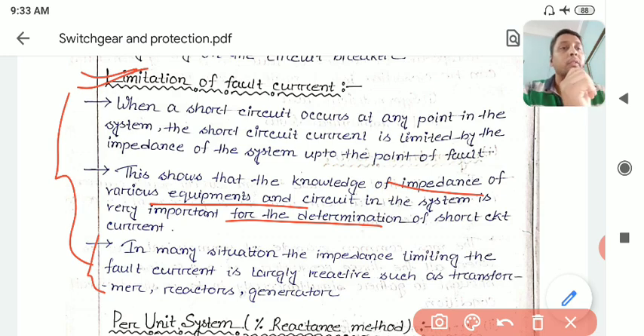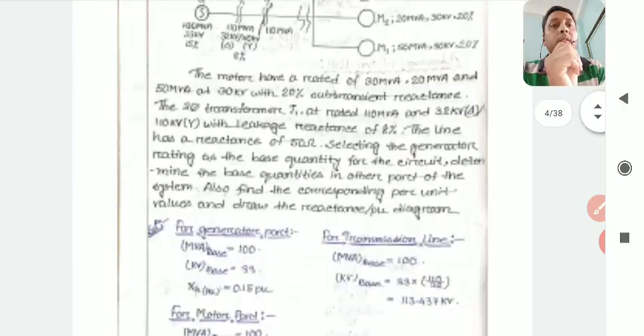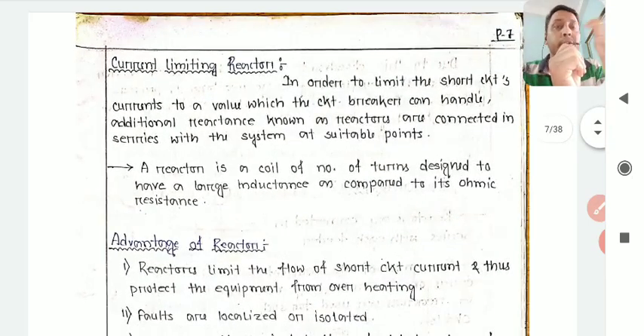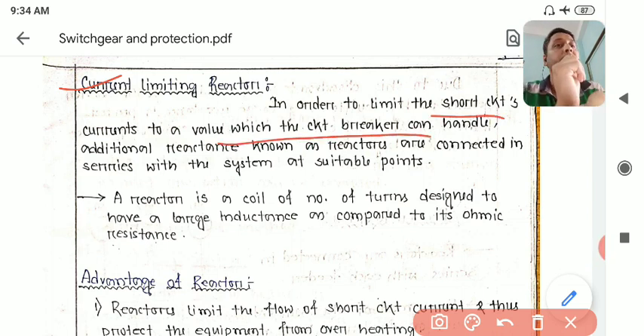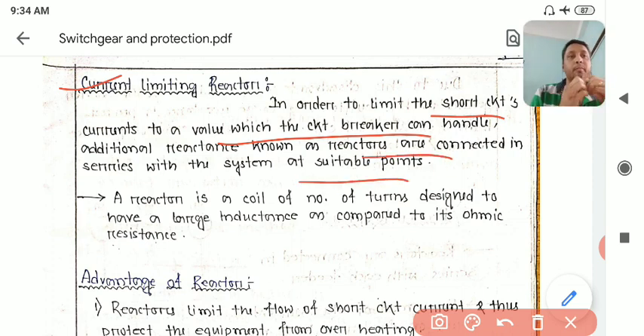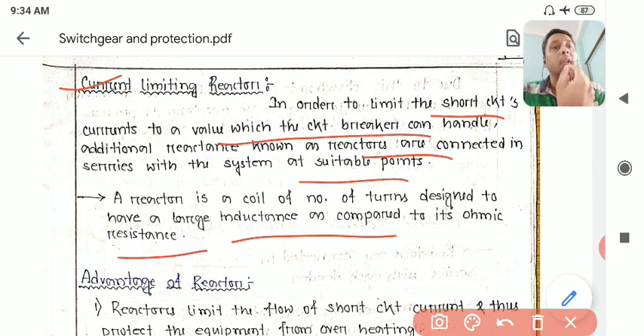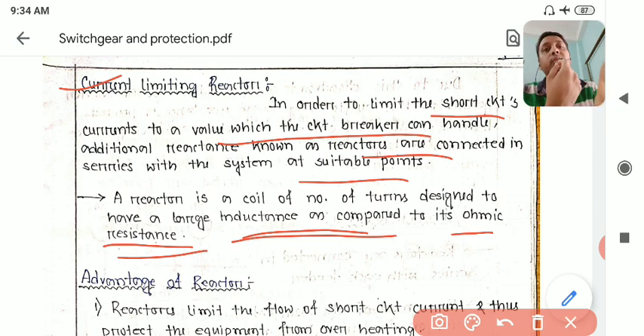For this purpose, we use items known as fault limiting reactors. There are different types of fault current limiting reactors. In order to limit the short circuit current to a value that the circuit breaker can handle, additional reactances known as reactors are connected to the system. A reactor is a coil of a number of turns having large inductance relative to its ohmic resistance. The ohmic resistance is made negligible and inductance is kept high, because we want the I²R heat drop and voltage drop to be minimal.